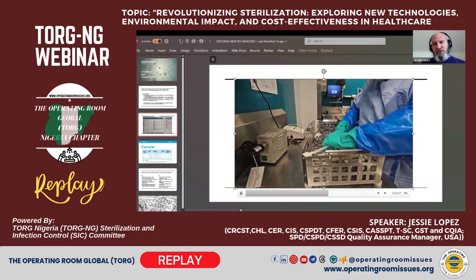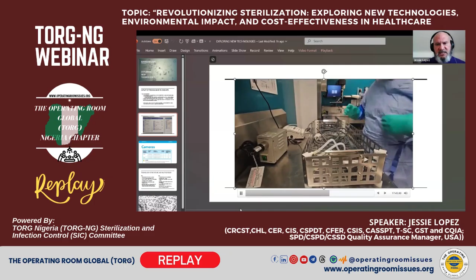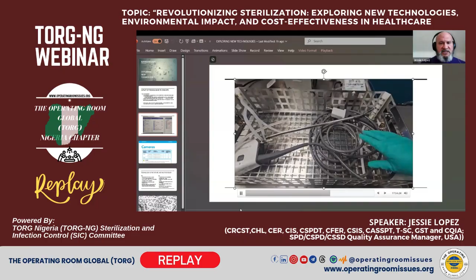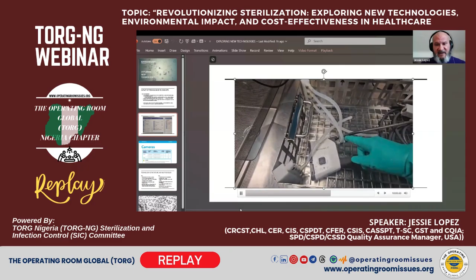This ultrasonic cleaner, irrigator, disinfector is going to eliminate all those steps where it's going to flush the internal lumens with detergent. It's going to rinse the internal lumens with deionized water. It's going to use overhead sprays to rinse the surface. And again, this ultrasonic cleaner and the IFU of this device is one device at a time. Okay, so if you have 3 or 4 of these devices, you're going to have to dedicate an employee to just clean robotic instrumentation because of the time.